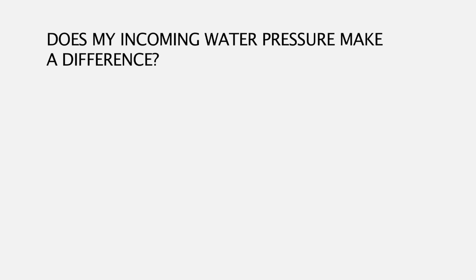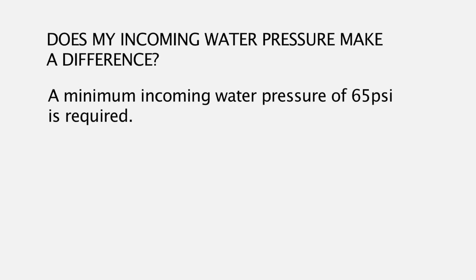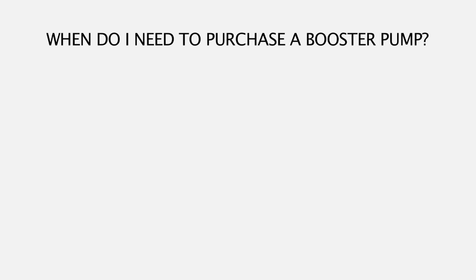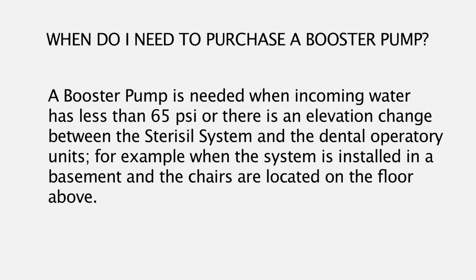Does my incoming water pressure make a difference? A minimum incoming water pressure of 65 psi is required. When do I need to purchase a booster pump? A booster pump is needed when incoming water has less than 65 psi, or there is an elevation change between the Sterisil system and the dental operatory units. For example, when the system is installed in a basement and the chairs are located on the floor above.